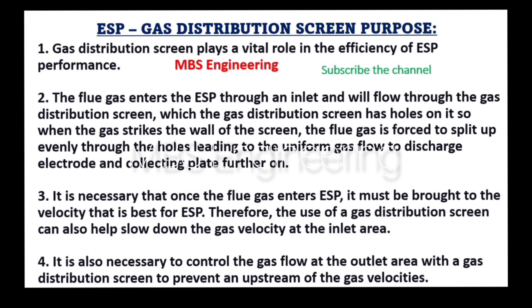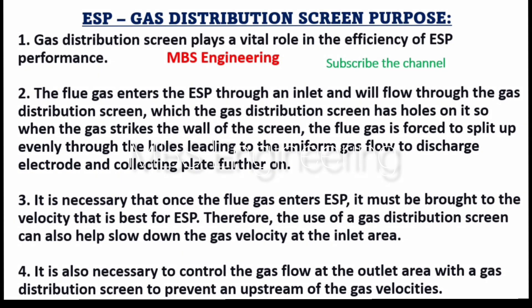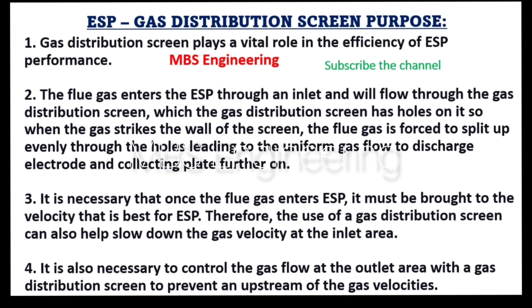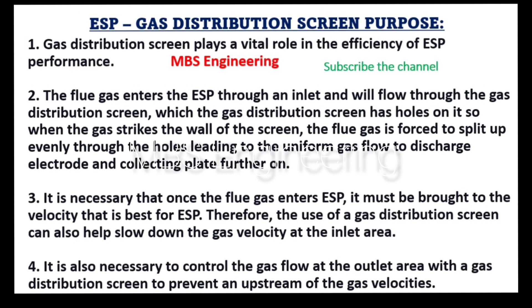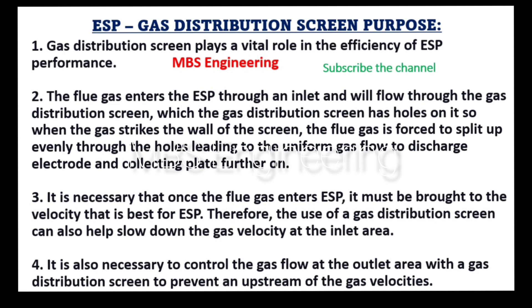Point 3: It is necessary that once the flue gas enters the ESP, it must be brought to the velocity that is best for ESP. Therefore, the use of a gas distribution screen can also help slow down the gas velocity at the inlet area. Point 4: It is also necessary to control the gas flow at the outlet area with a gas distribution screen to prevent upstream of the gas velocities.